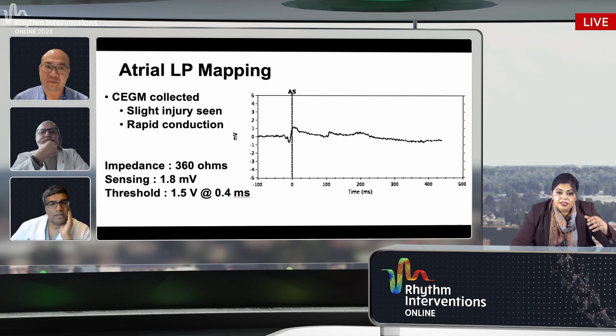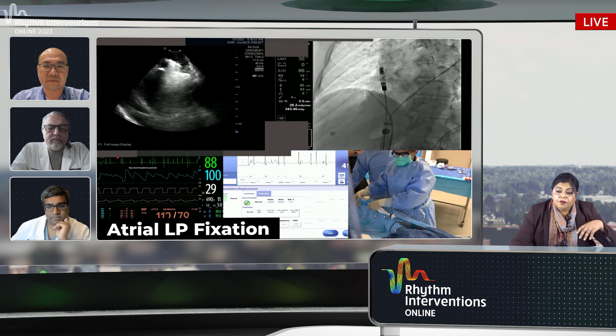And once we know we have good numbers, we're getting ready to fixate, and I'm turning the blue knob, slow cadence. It's a straight shot, so you'll see that chevron on fluoroscopy move, and we're looking for about 1.5 turns, and we'll watch that very closely on fluoroscopy to make sure we don't go past. The footprint of the helix is big, but the helix as such is not as deep. So very slow rotations. And once we have done the 1.5 turns, we'll undock the device.